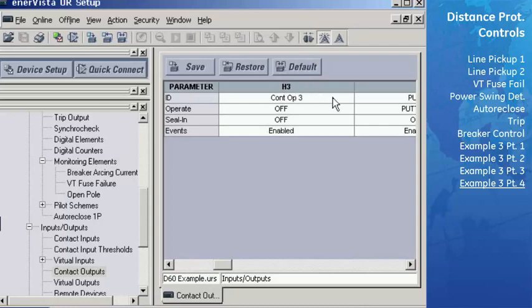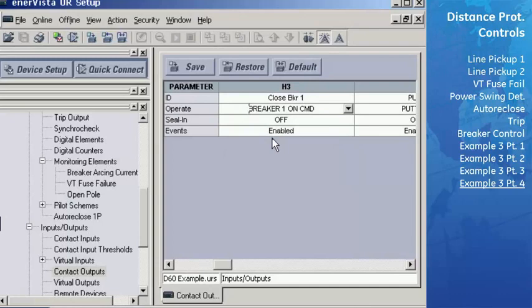Change the name of H3 to Close Breaker 1, since this contact will be used for closing and reclosing the breaker. Change the operate signal of this breaker to breaker 1 on command. This is the close command from the breaker control function. Save these settings and close the window. Now, all of the settings necessary to put our example D60 relay into service have been completed.